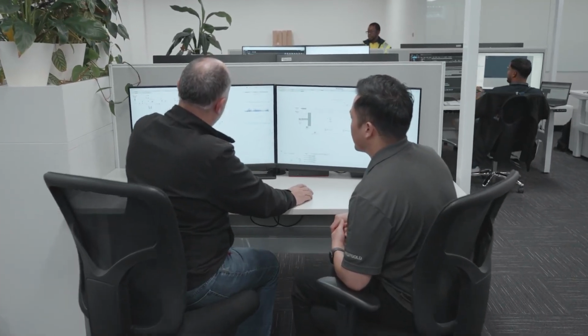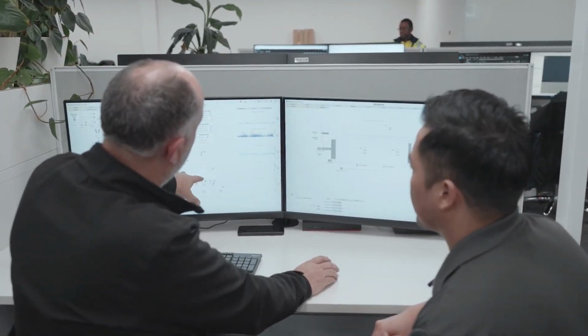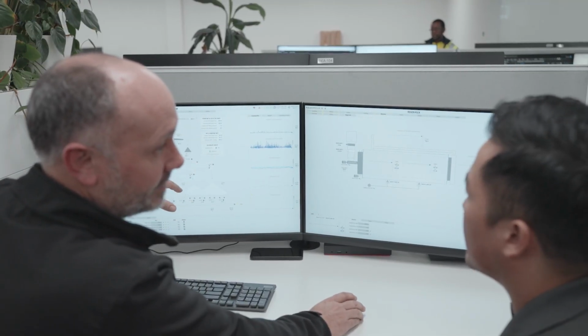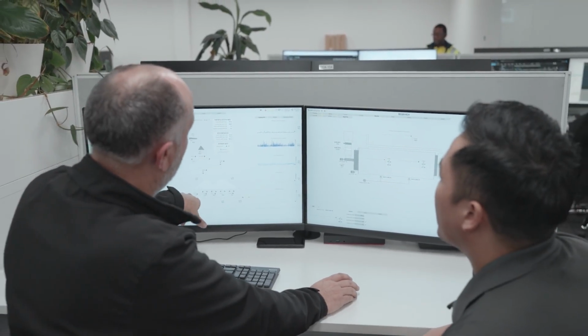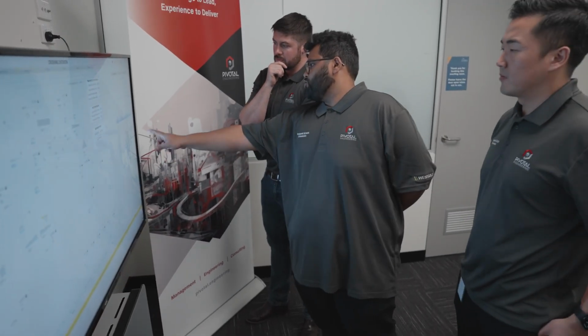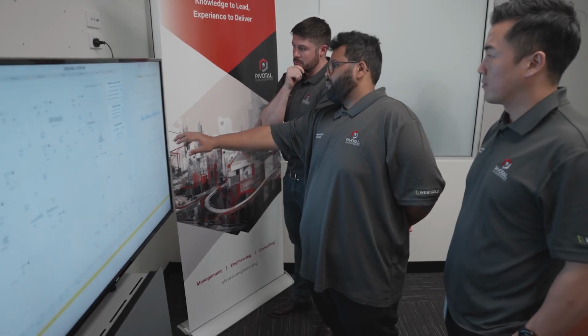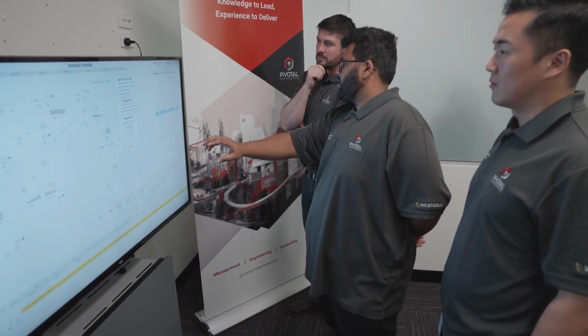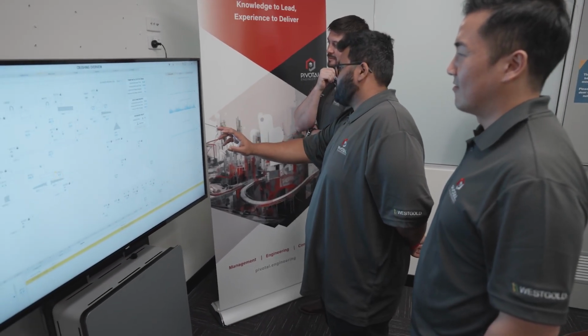One of the things our engineers had to look into was the firmware versions on the PLCs, driver compatibility, and the mix of different PLC versions on site, since they hadn't been updated recently. That meant a technical challenge: upgrading those PLCs to the right firmware without incurring shutdowns, while not investing too much time into a legacy system that would be decommissioned at the end of this project.